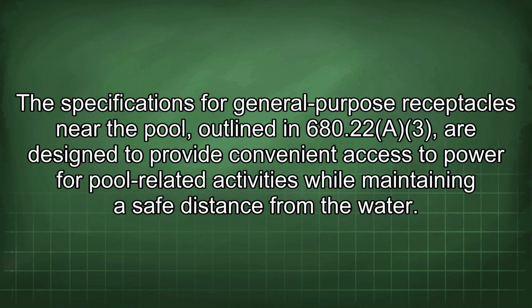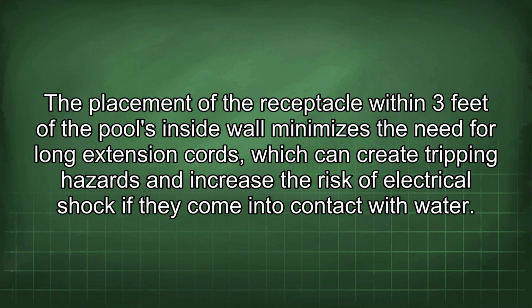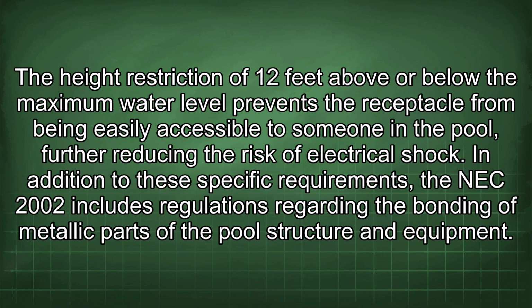The specifications for general-purpose receptacles near the pool, outlined in 680.22(A)(3), are designed to provide convenient access to power for pool-related activities while maintaining a safe distance from the water. The placement of the receptacle within 3 feet of the pool's inside wall minimizes the need for long extension cords, which can create tripping hazards and increase the risk of electrical shock if they come into contact with water. The height restriction of 12 feet above or below the maximum water level prevents the receptacle from being easily accessible to someone in the pool, further reducing the risk of electrical shock.